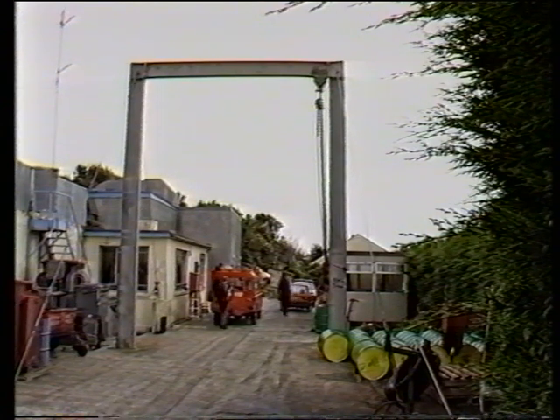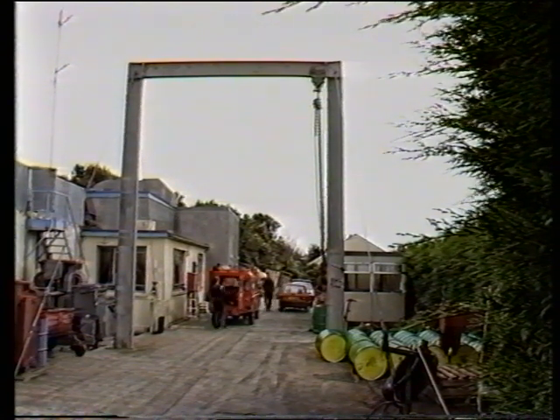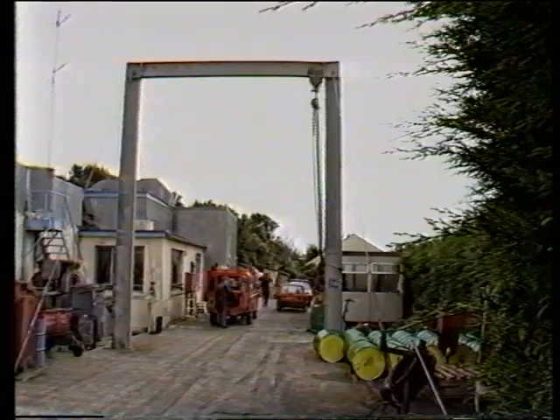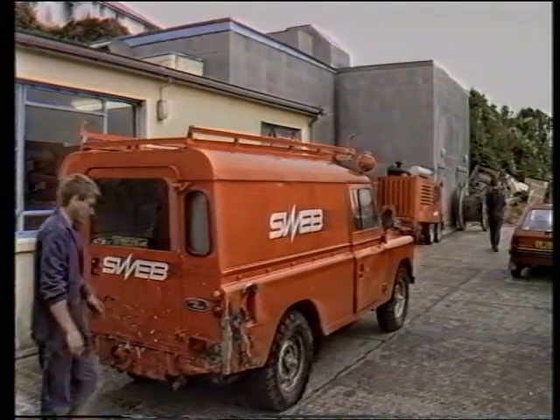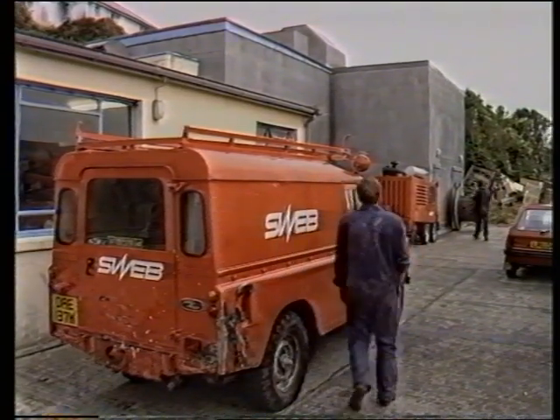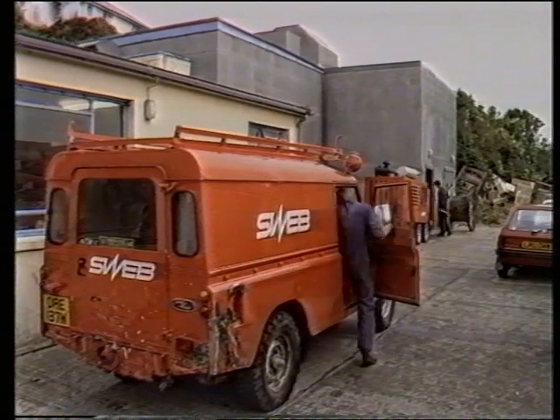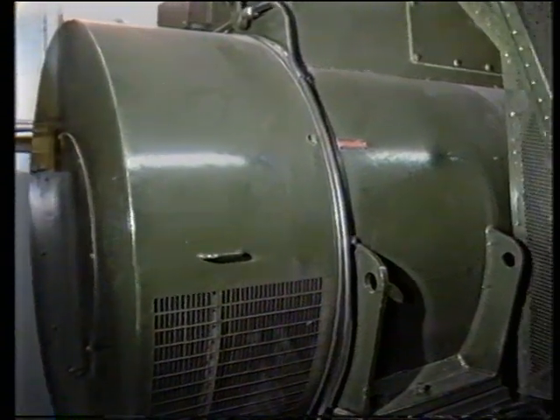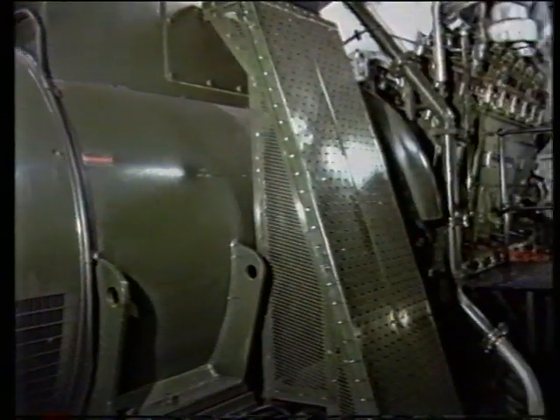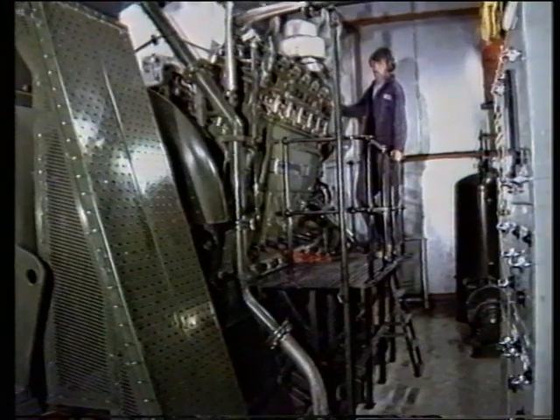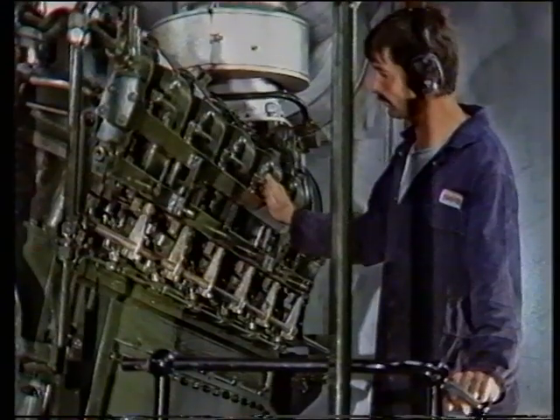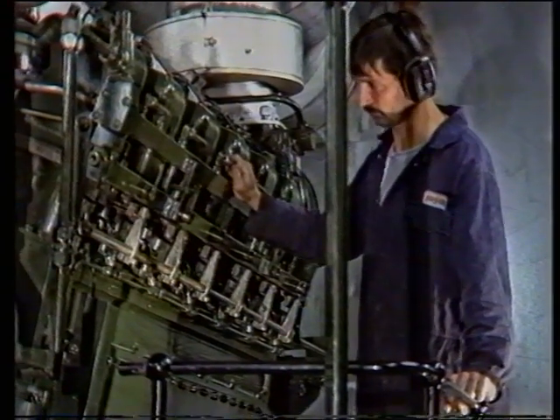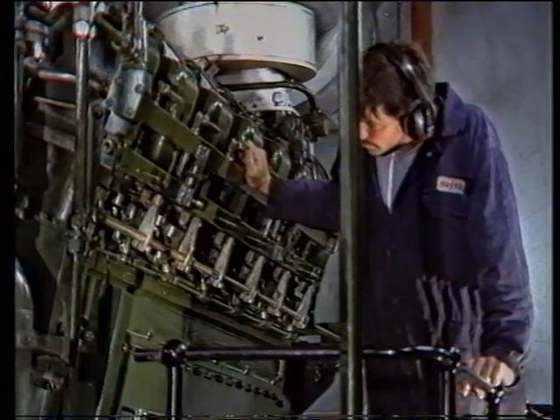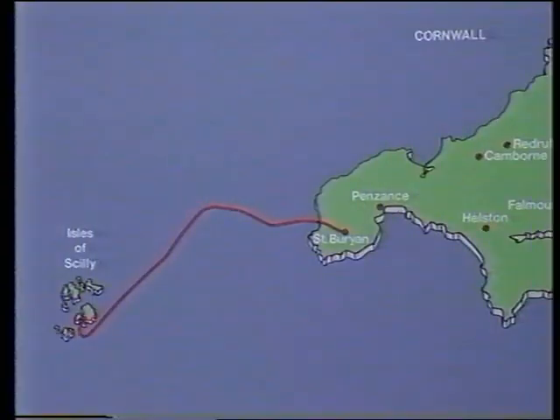from Penzance. Until 1985, it supplied electricity only to St Mary's. Then, submarine cables were laid to the outer islands, and the Scillonians out there switched off their own expensive-to-run generators and switched on to Sweb. But with electricity prices on the Scillys higher than the rest of the southwest because of higher fuel costs, the islanders pressed for mainland tariffs. Sweb agreed and decided to put the local generators into reserve and run a 33,000-volt cable link from the mainland.